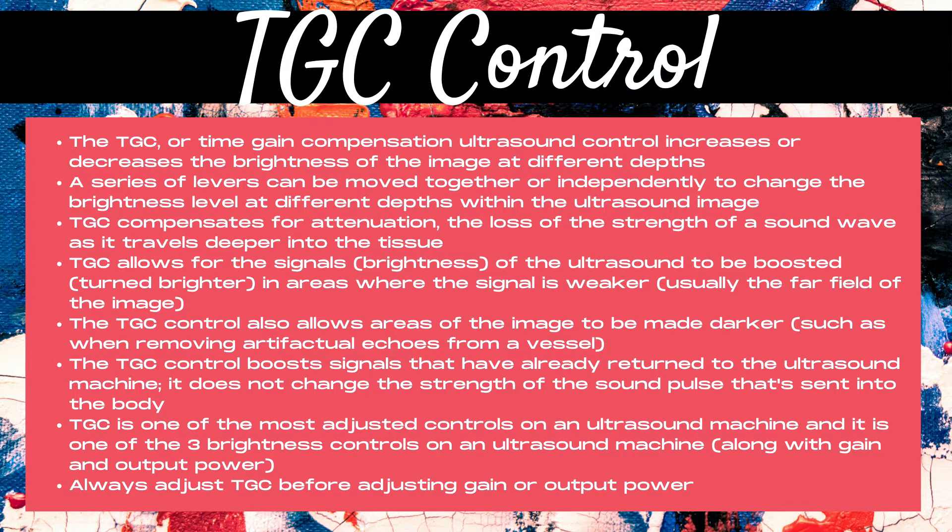TGC is one of the most adjusted controls on an ultrasound machine, and you should always adjust the TGC before adjusting the output power or the gain.